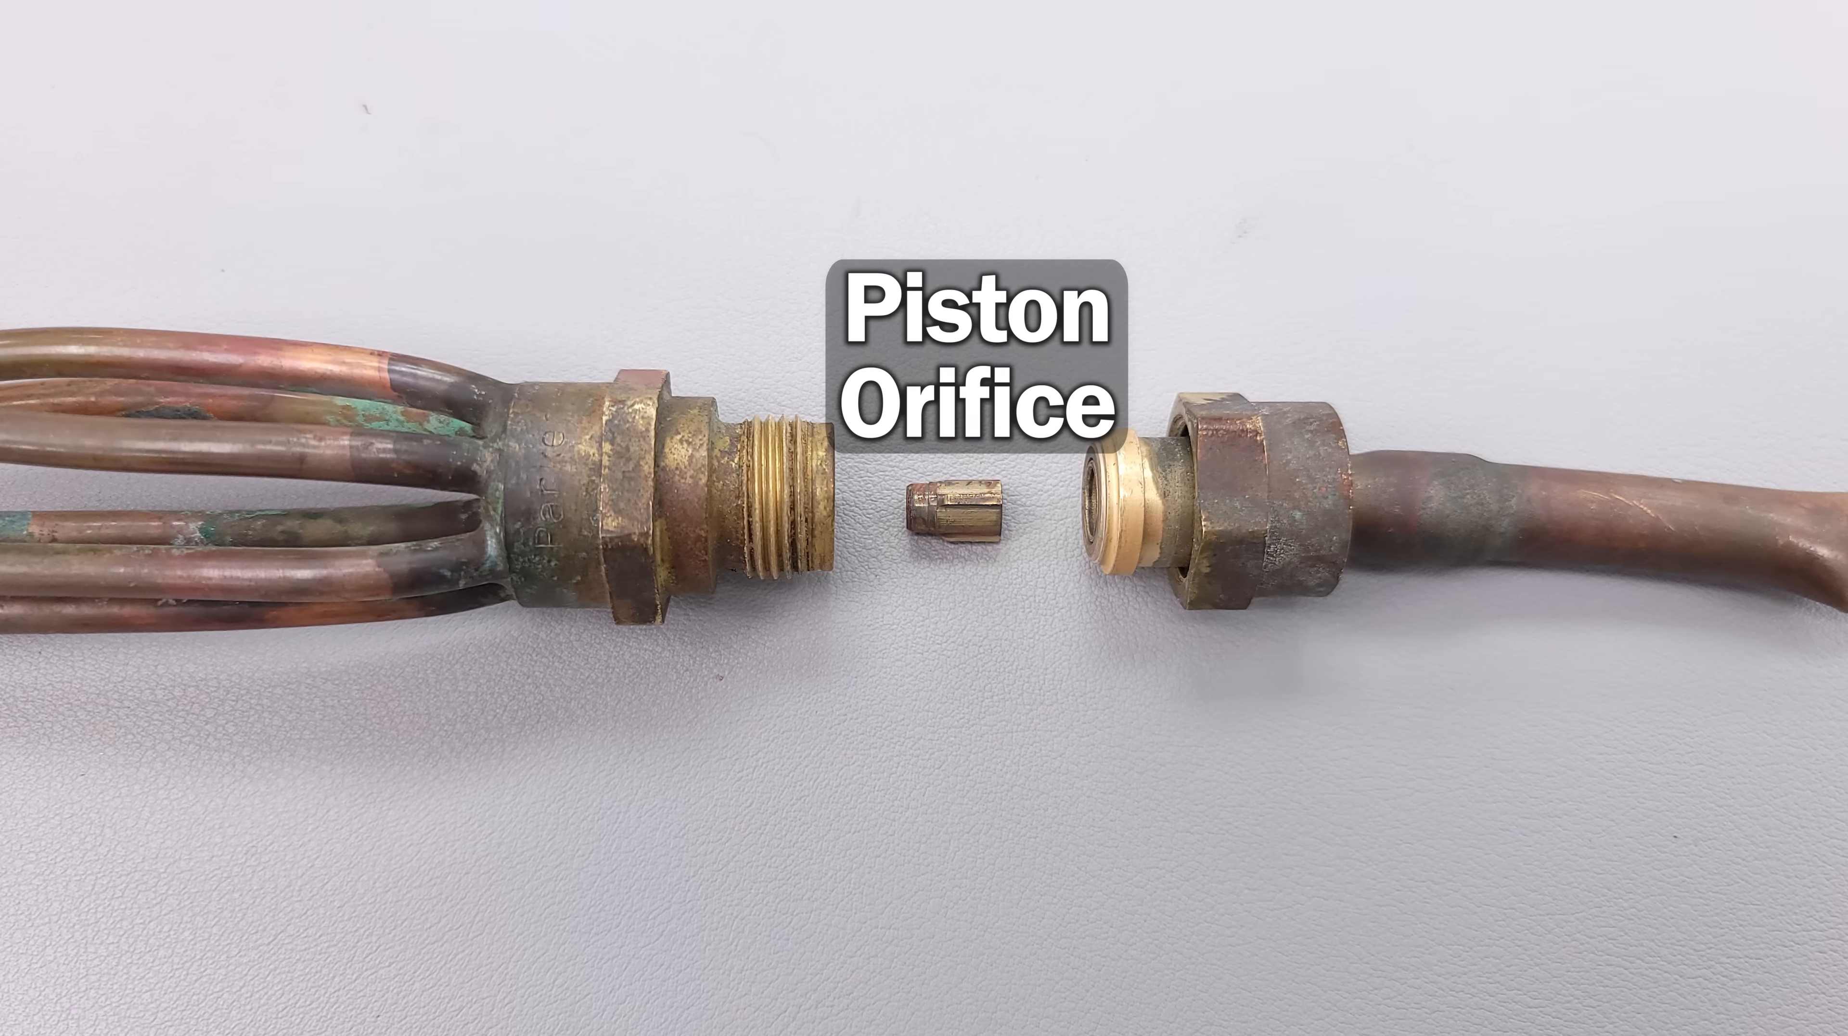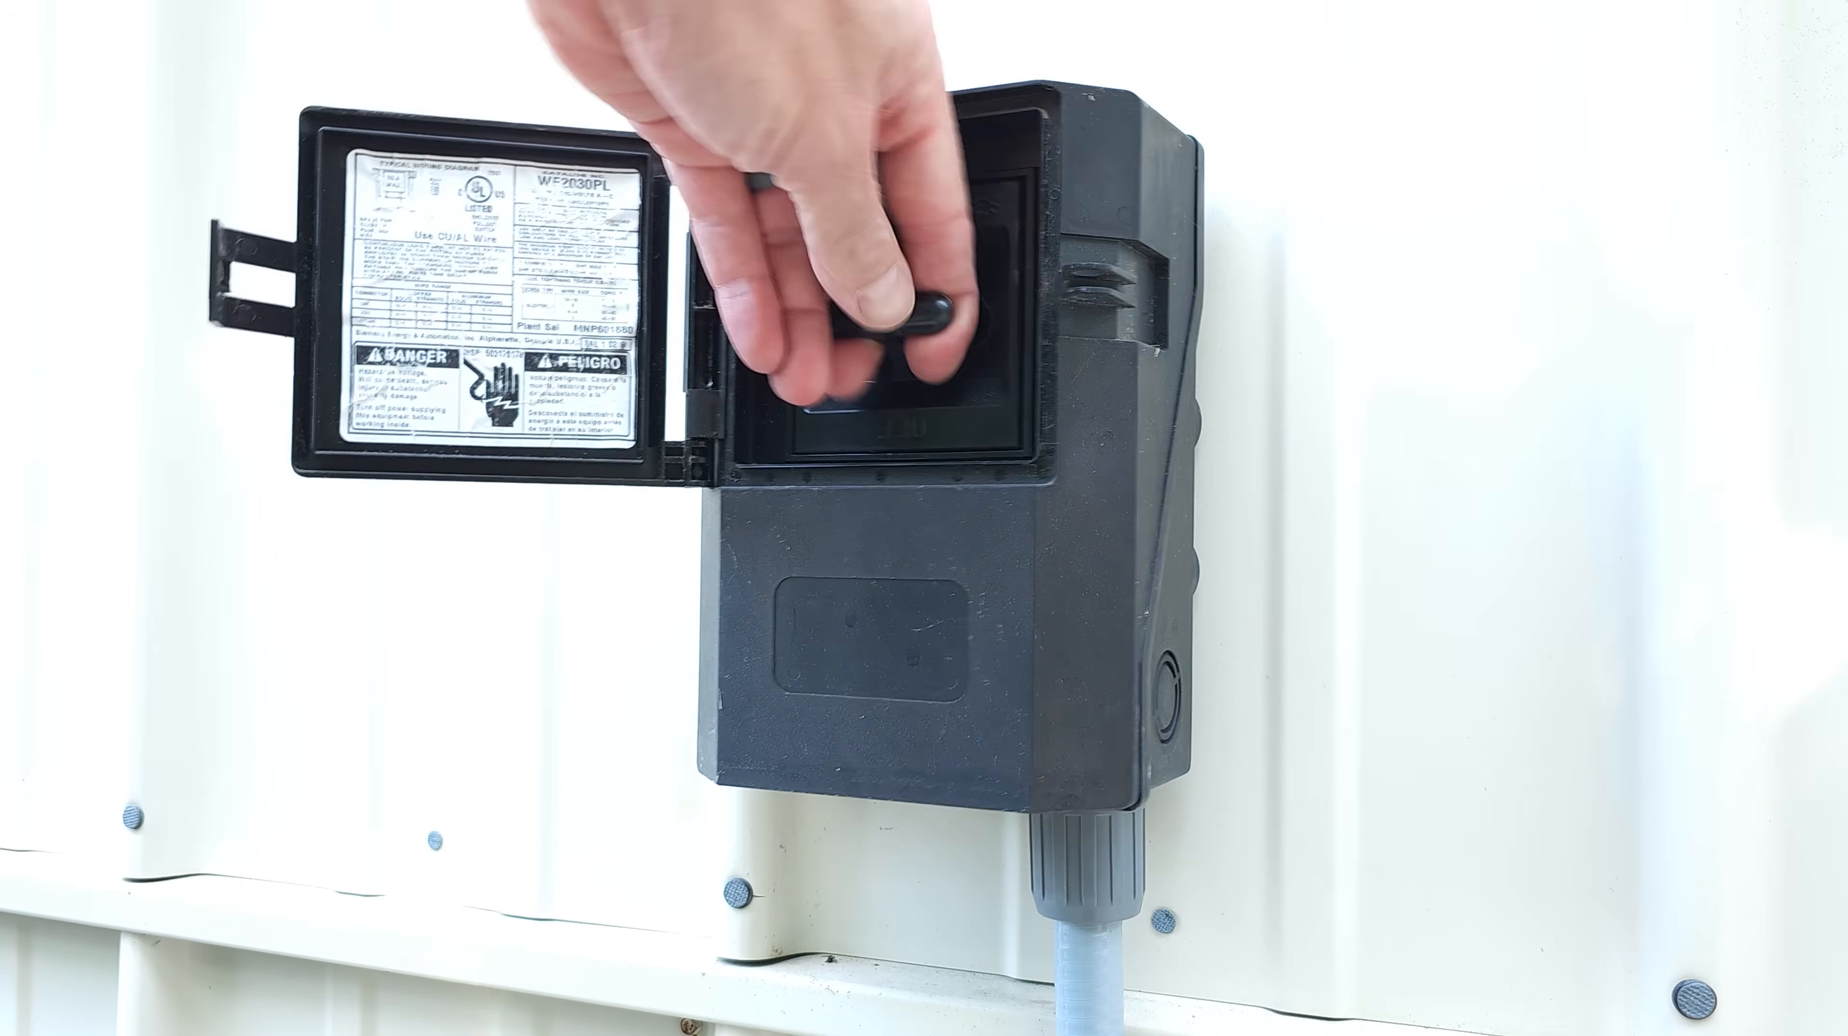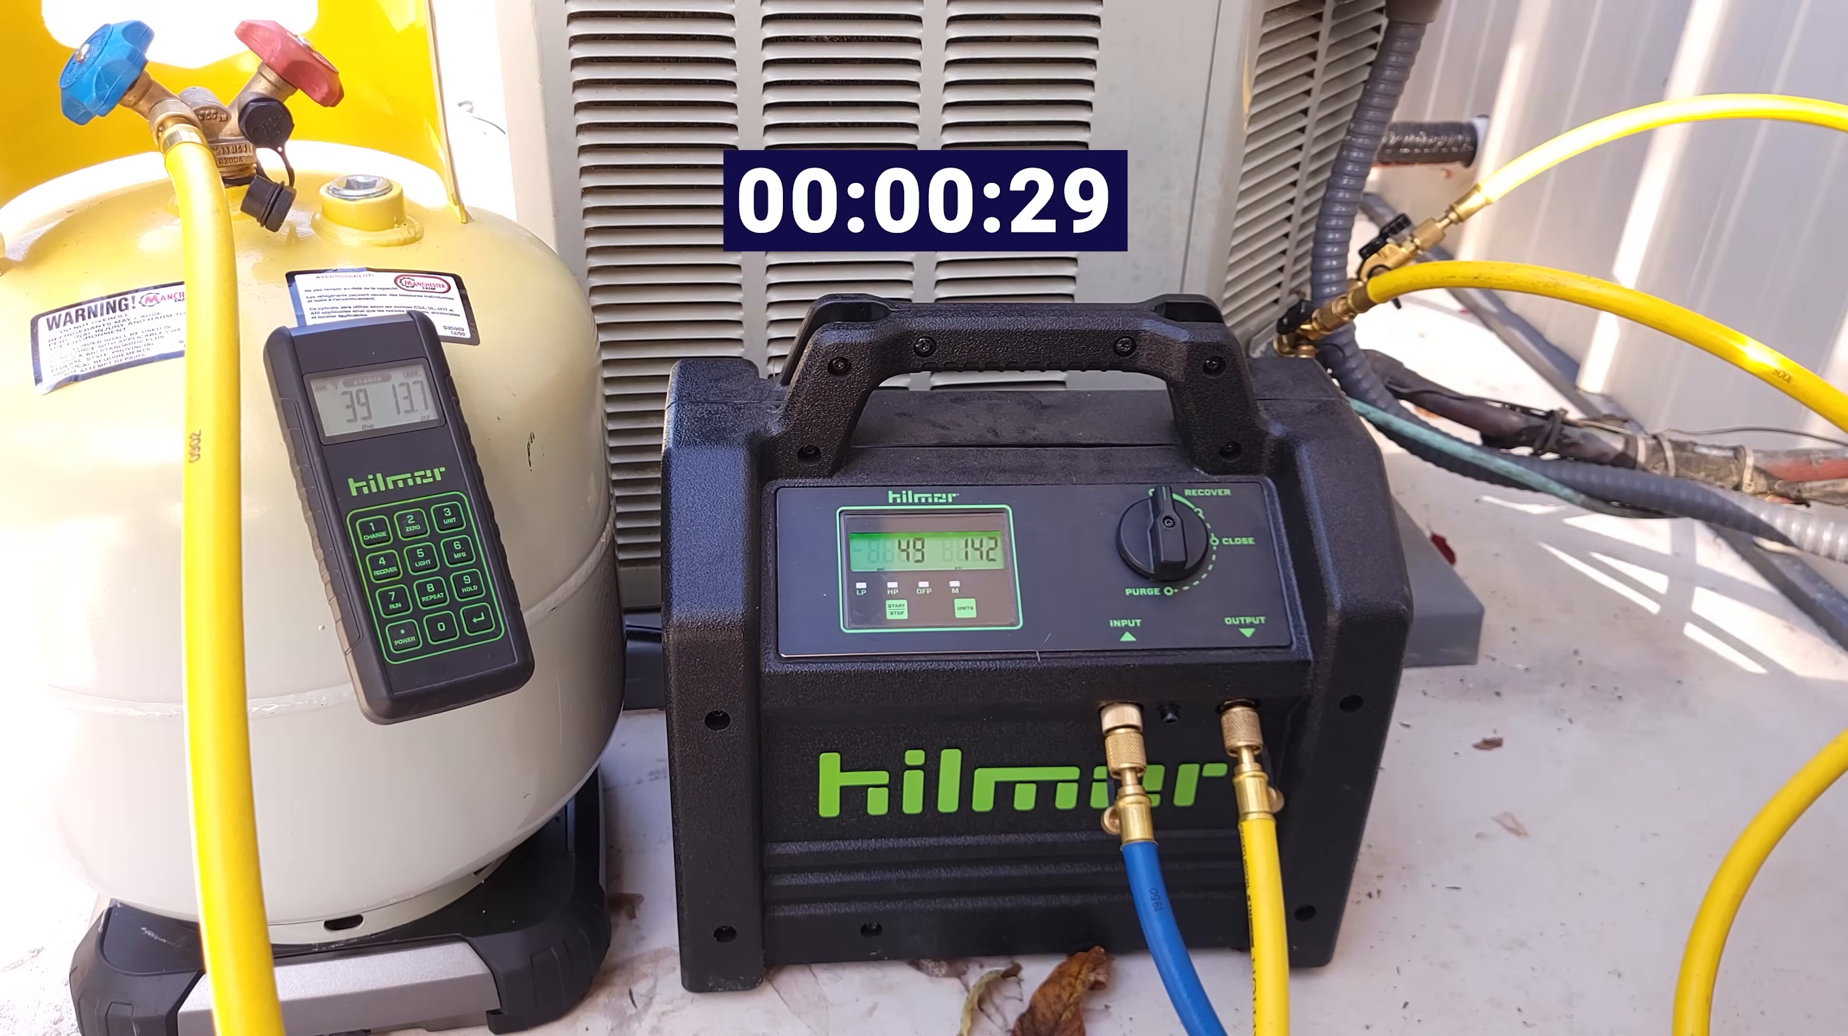In this video, I want to show you how to replace a piston with a TXV metering device. The first thing you'll need to do is turn the power off to the system and recover the refrigerant out of the unit.